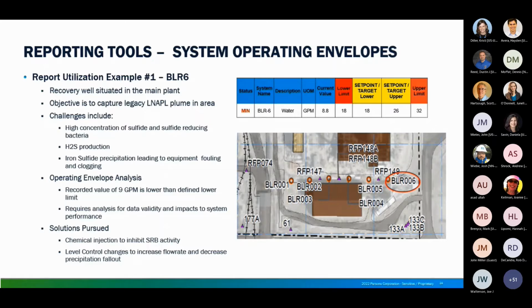So we can see on top the cutaway of the operating envelope. The weekly data collected by the technician indicates that we've got 9 gallons a minute coming out of this particular BLR6. That's obviously a lot lower than the defined lower limit. So that indicates to us right away that this needs additional analysis.